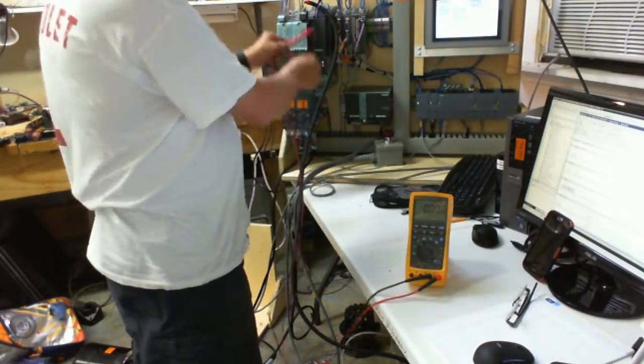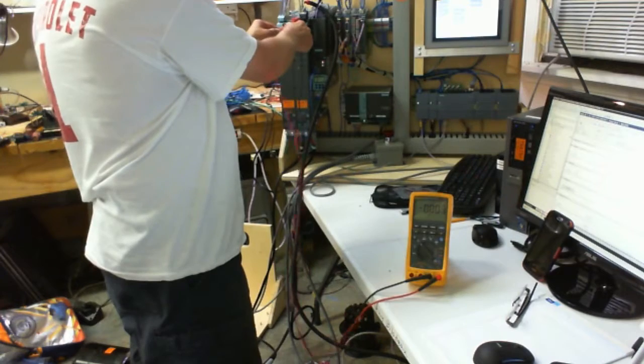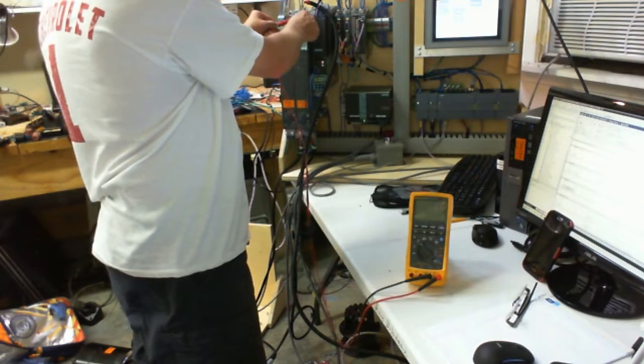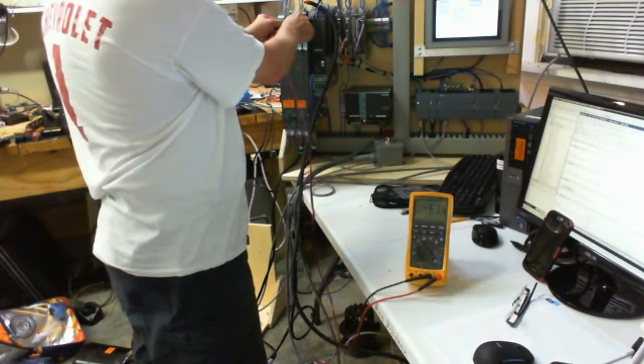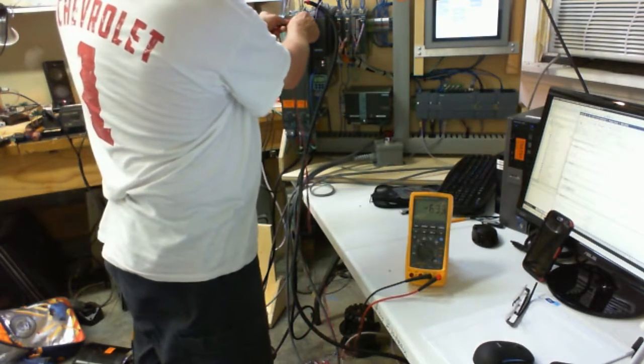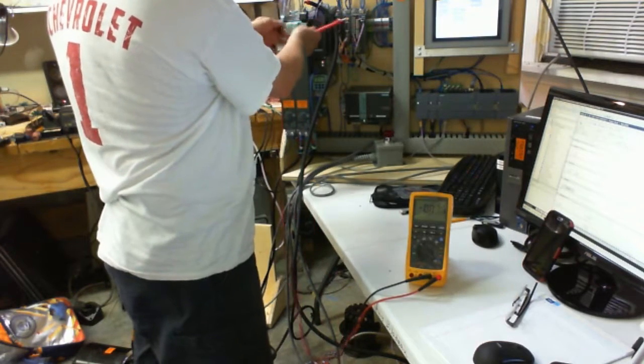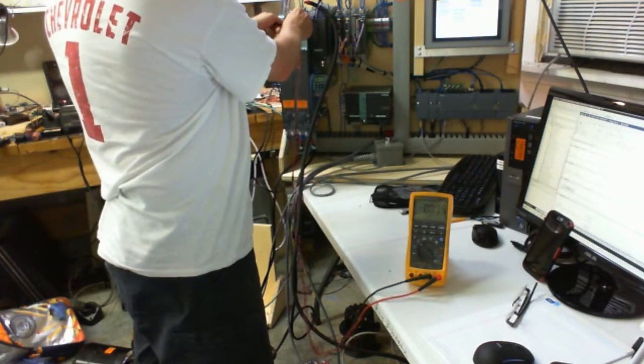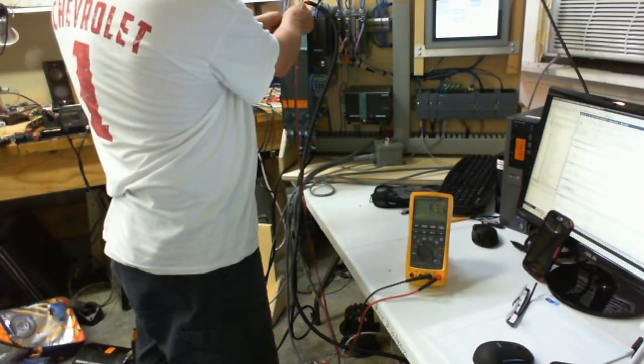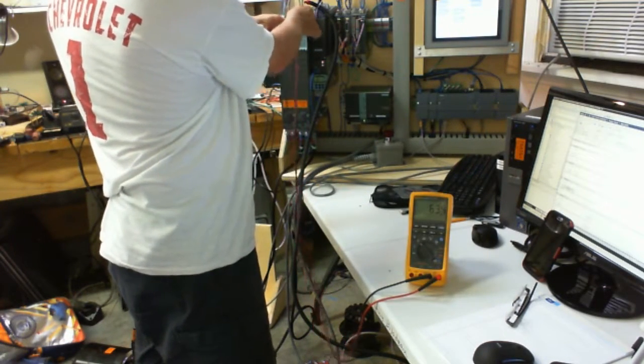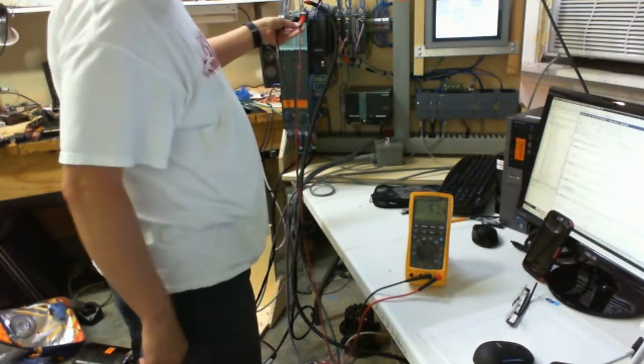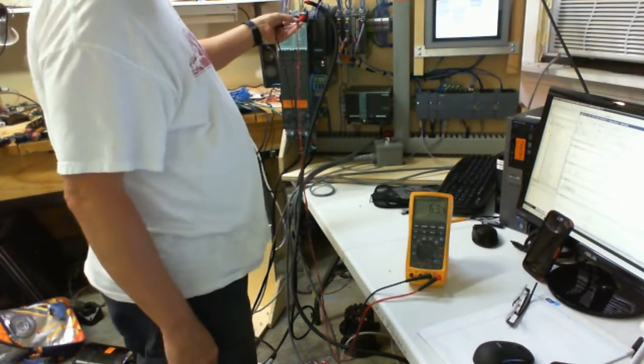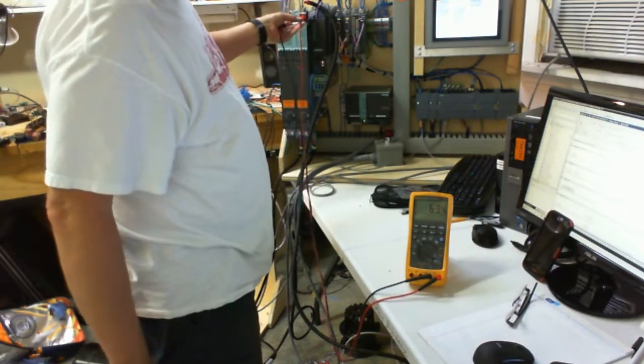You always take your meter. On this drive, I can actually get to the bus on the outside. You see this guy's running about 630 volts DC. Way more than is needed to kill you.